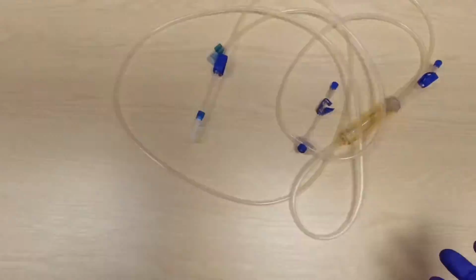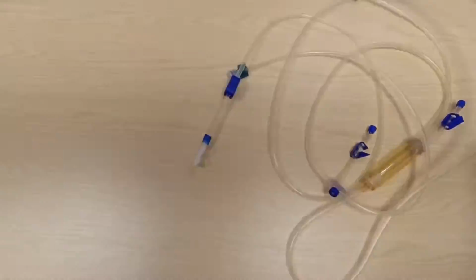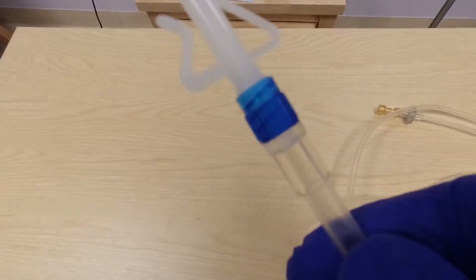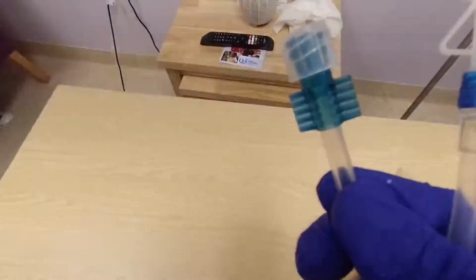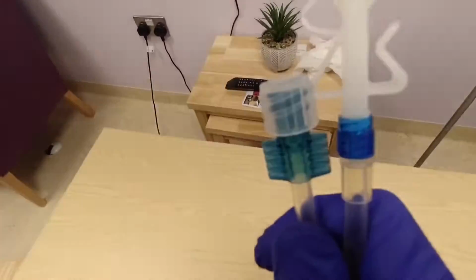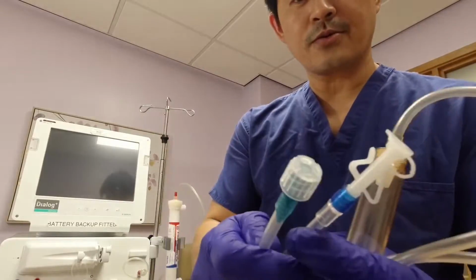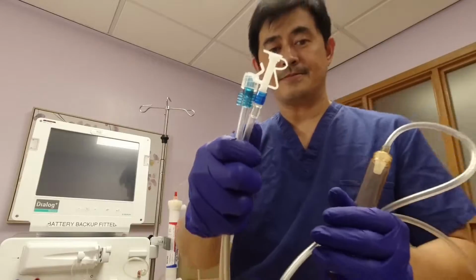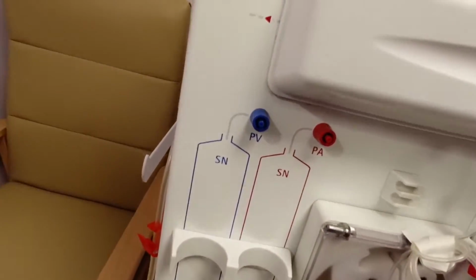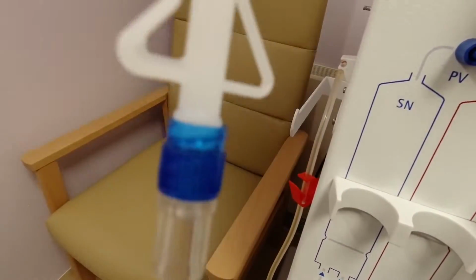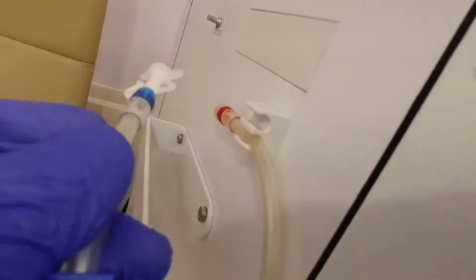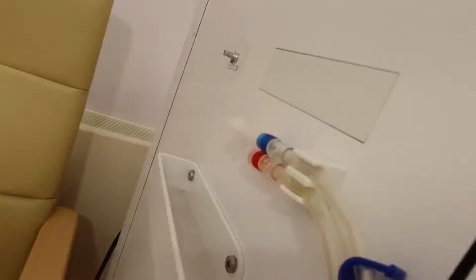Your venous line is your blue line. It's pretty much the same looking. There are two ends on the line again, similar to the arterial line. The end we're looking for is the one that will be connected to the patient, and the other one is this funny looking shape end which is connected to your dialyzer. I'm going to grab hold of these two ends again, the patient line and the dialyzer line. Setting up the venous line is pretty much the same as your arterial line. Holding the patient line here, that's going to go on the side of the machine there. There you are.